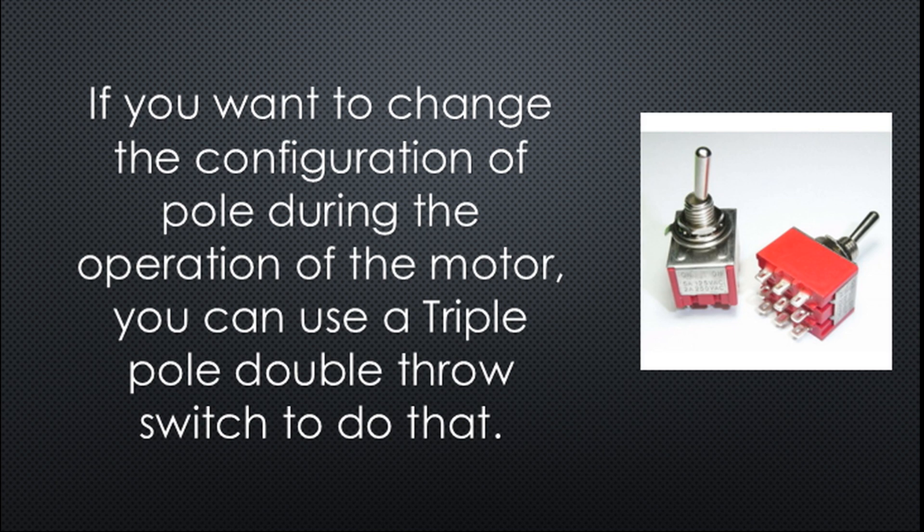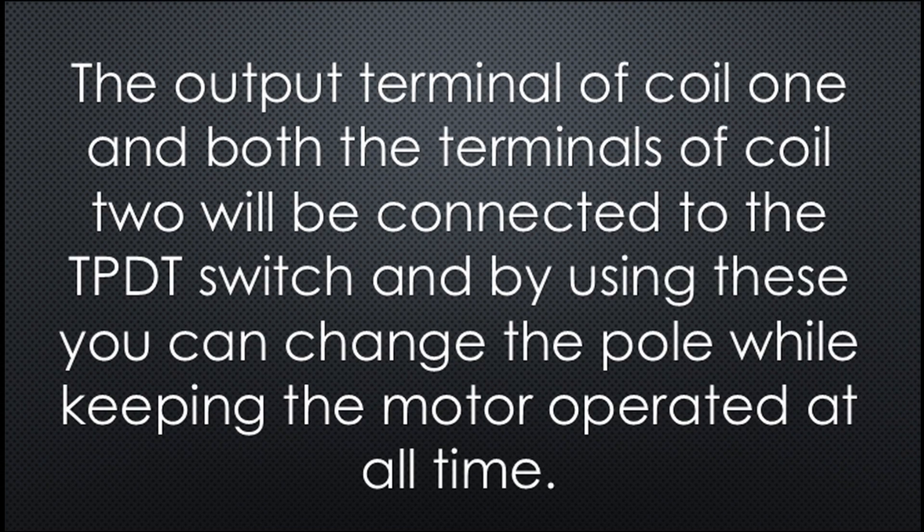If you want to change the configuration of pole during the operation of the motor, you can use a triple-pole double-throw switch to do that. The output terminal of coil one and both the terminals of coil two will be connected to the TPDT switch, and by using this you can change the pole while keeping the motor operated at all times.